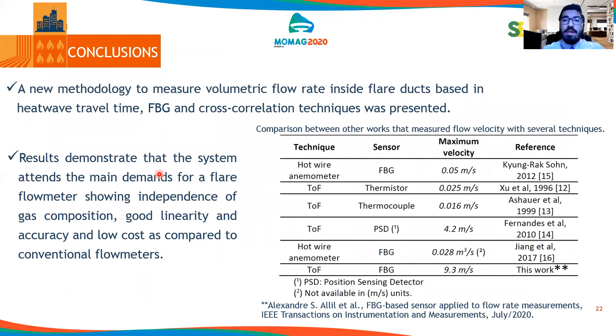Our conclusions. A new methodology to measure volumetric flow rate inside flare ducts, based on heatwave travel time, FBG, and cross-correlation techniques, was presented. We have also published an article in IEEE Transactions on Instrumentation and Measurements in July 2020, where comparing our work — represented on the last line of the table — using the time-of-flight technique and FBG sensors, we achieved the highest velocity by far compared to other authors in the literature.